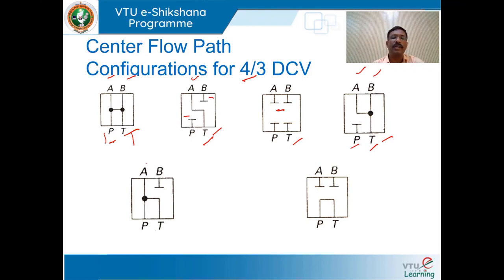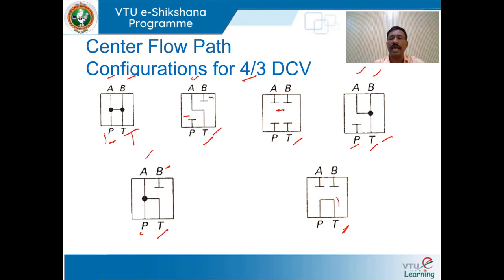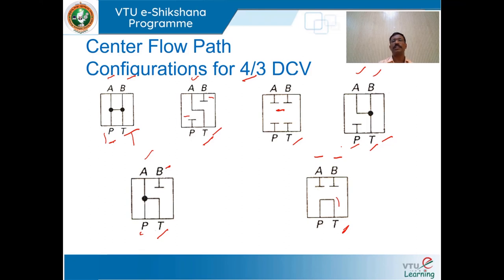Another configuration has A and P open to tank but port B is blocked. The last is the tandem type center flow path configuration, where P is open to tank and ports A and B are closed. These are the six different center flow path configurations for a 4-way 3-position directional control valve.